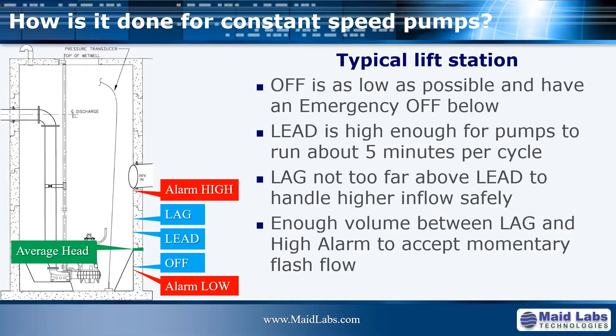So if you want to use a flow-based operating system on your lift station, how will you do that? First, you have to set the lowest safe level. Usually it's the actual off level that you already have in your lift station. What is the highest safe level? When the flow rate is very low, historically it has been low at that time of the day, there's no rain in the forecast, and it's not raining right now, there's no reason for one pump not to be able to pump that down very rapidly. Then this is the highest safe level. So you need to enter that.